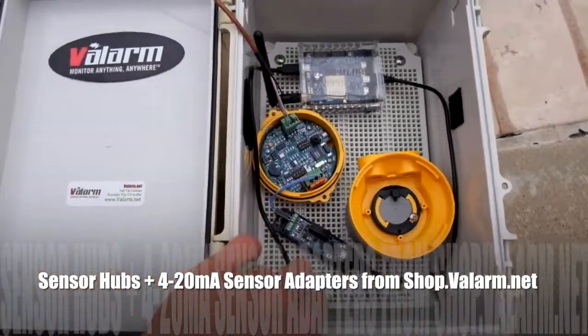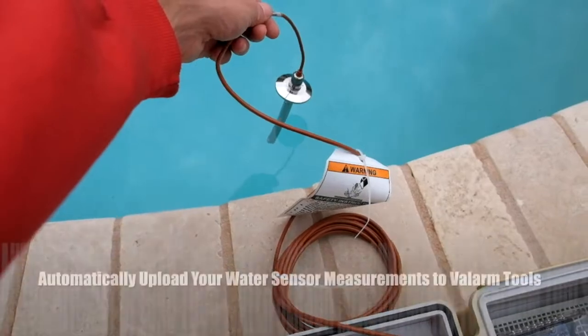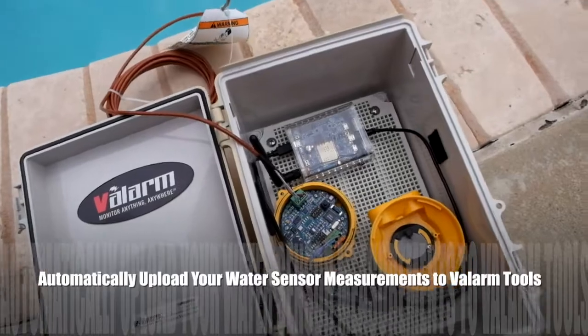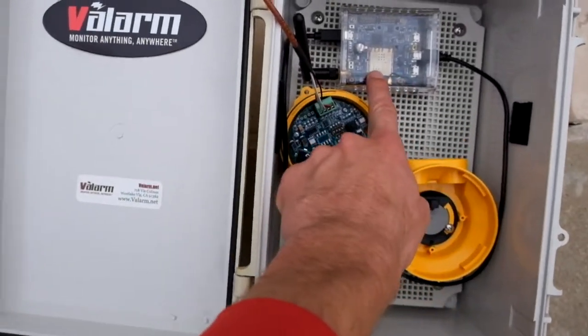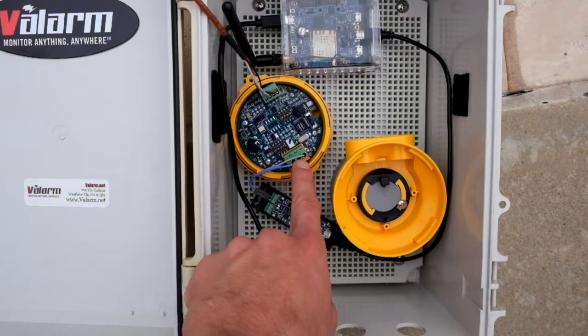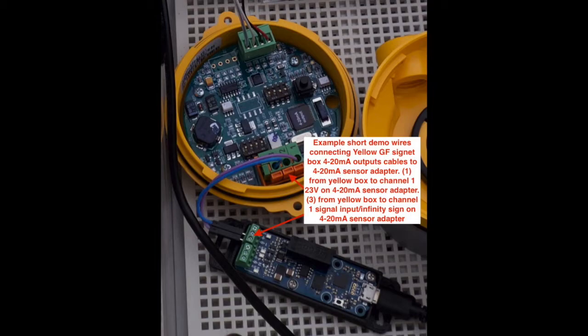These sanitary sensors monitor water quality factors like conductivity or resistivity and output water sensor readings as 4 to 20 mA signals, which is a common industry standard. The V+ or positive output from your GF Signet sensor box connects to the 23V input on channel 1 of your 4 to 20 mA sensor adapters. The V- or negative connectors go into your channel 1 signal input, which kind of looks like an infinity sign.